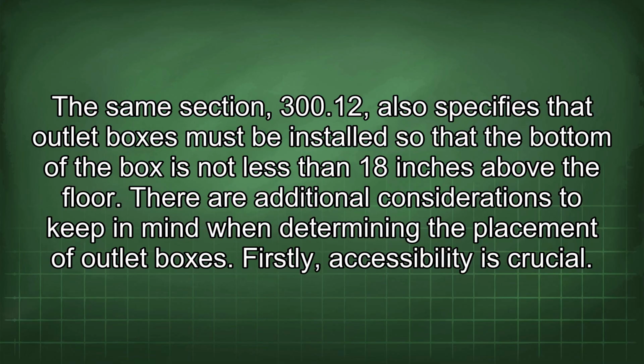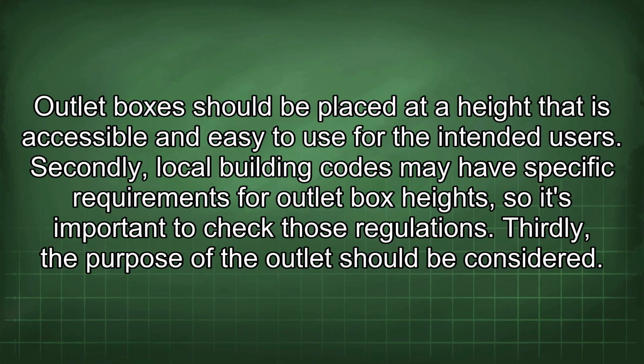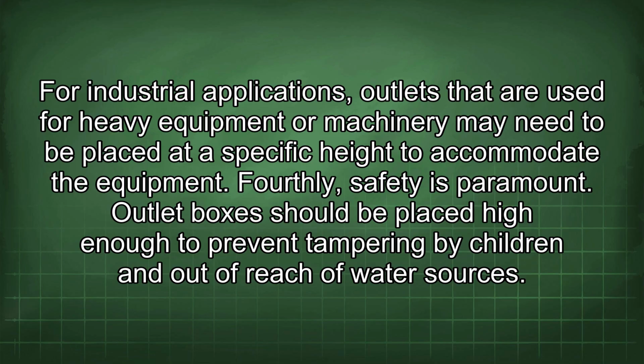There are additional considerations to keep in mind when determining the placement of outlet boxes. Firstly, accessibility is crucial - outlet boxes should be placed at a height that is accessible and easy to use for the intended users. Secondly, local building codes may have specific requirements for outlet box heights, so it's important to check those regulations. Thirdly, the purpose of the outlet should be considered - for industrial applications, outlets used for heavy equipment or machinery may need to be placed at a specific height to accommodate the equipment.